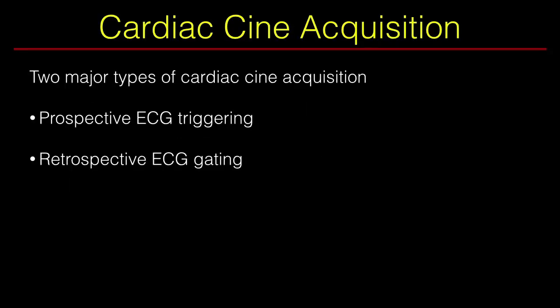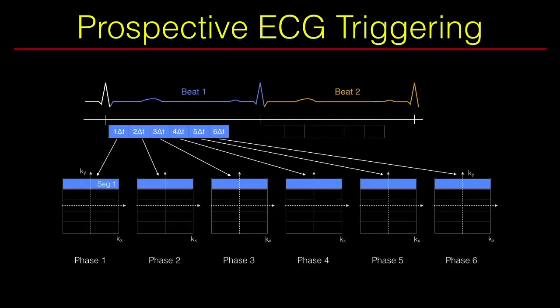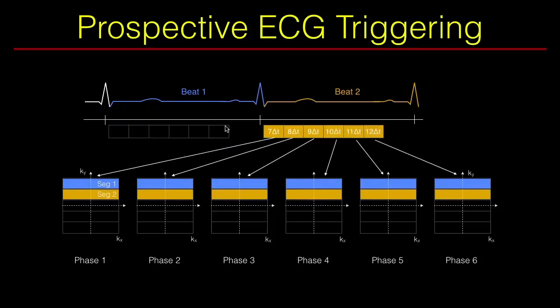We acquire cardiac cine images with either prospective ECG triggering or retrospective ECG gating. In prospective ECG triggering, as soon as we detect the QRS complex we acquire the first segment for all the cardiac phases. The acquisition duration is constant and defined to be less than the lowest RR interval. Once we see the next trigger pulse we acquire the second segment and fill it into k-space. The reconstruction is very simple — we combine the different segments, Fourier transform, and get the final cardiac cine images.